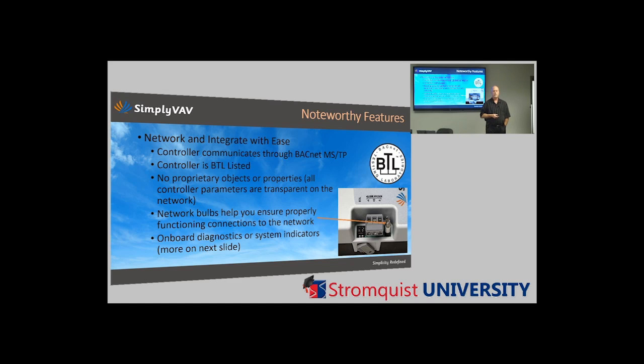We adhere to the BACnet standard fully, ASHRAE standard 135 from top to bottom. If you go on our website, on the Simply VAV website, you'll see our PICS statements there, which will tell you what you can read, what you can write to our controllers. Again, all standard objects, nothing proprietary, and it's all available on the website.